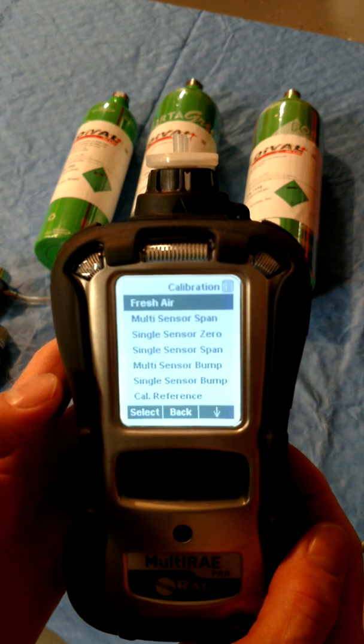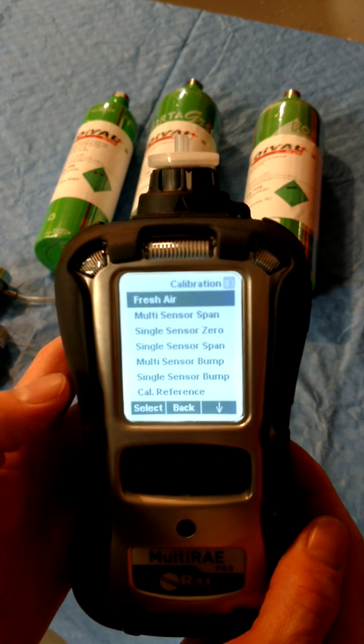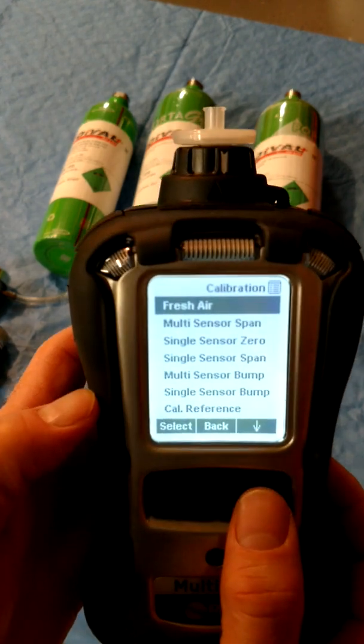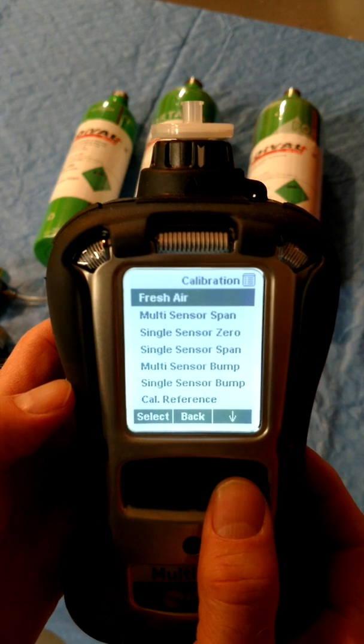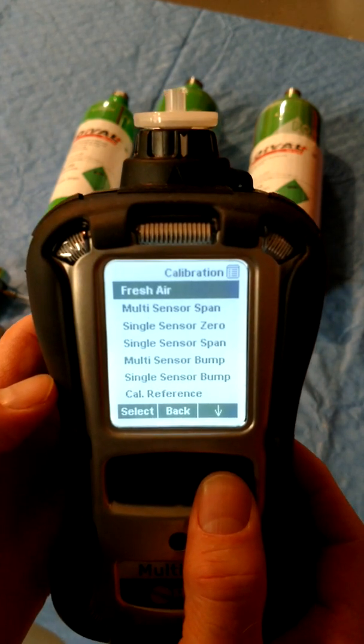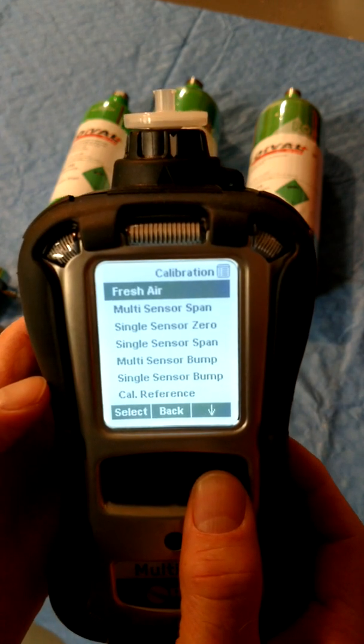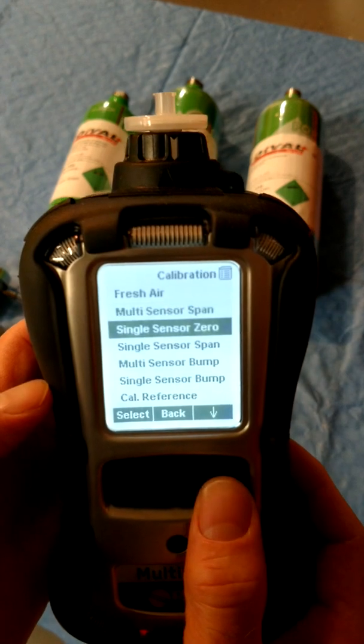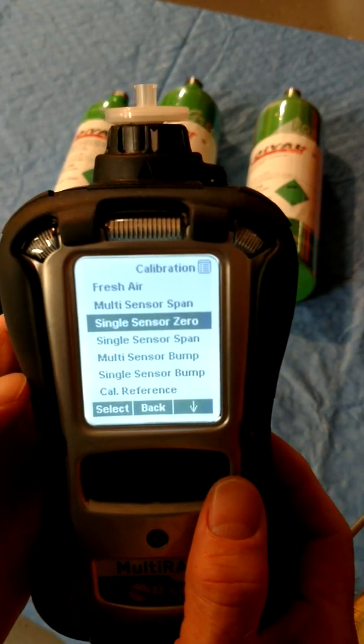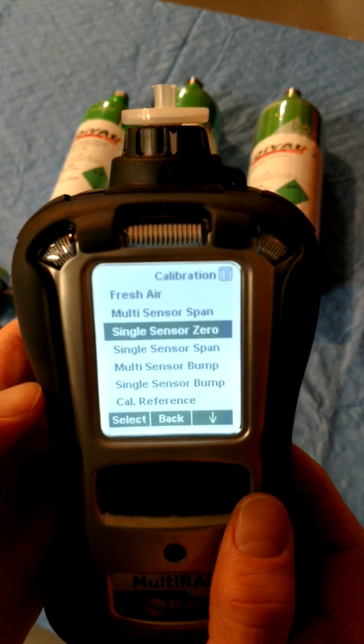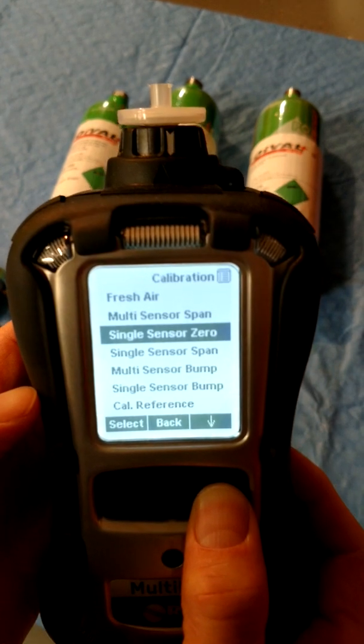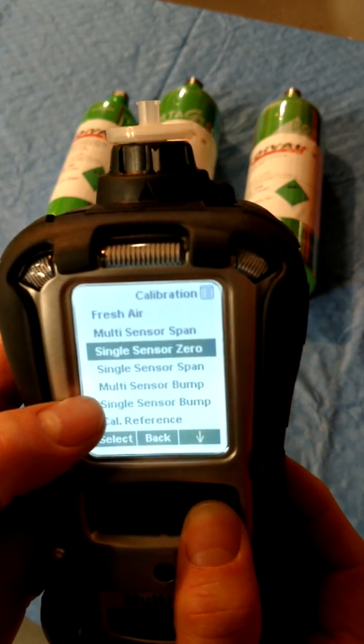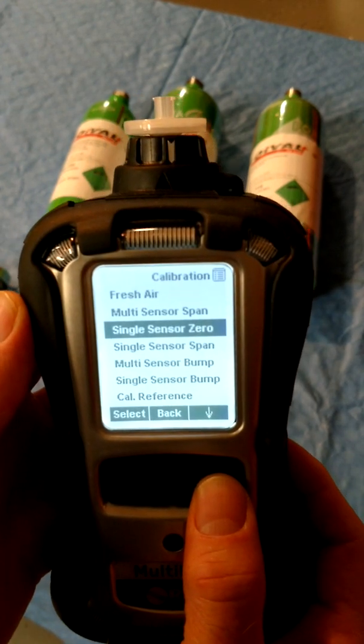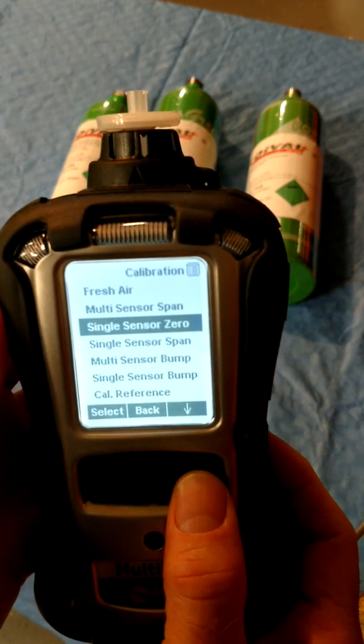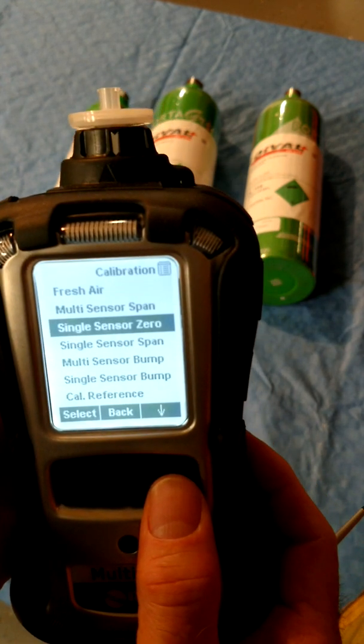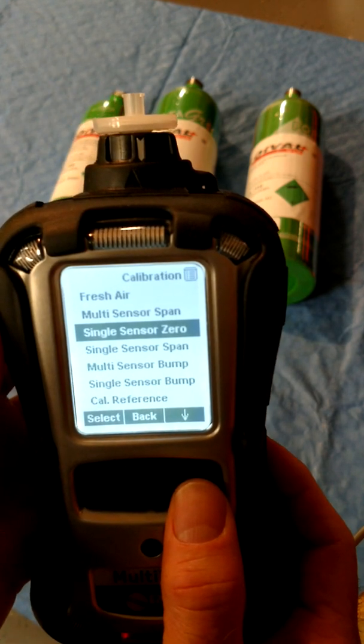Now I'll briefly cover the other types of calibrations that can be performed, but this video will only demonstrate the span cal. First on the menu is fresh air calibration. Fresh air calibrations simultaneously set the 0 point on all sensors that require a 0 cal. Fresh air calibration is required prior to hot zone entry. There is an option to 0 cal only one sensor at a time, single sensor 0. Typically not used. Bumping the meters under the multi-sensor bump and single sensor bump options are used to perform a qualitative function check of sensor response and alarm activation prior to use via a challenge gas. Bump tests differ from span calibrations in that they check function, not accuracy.